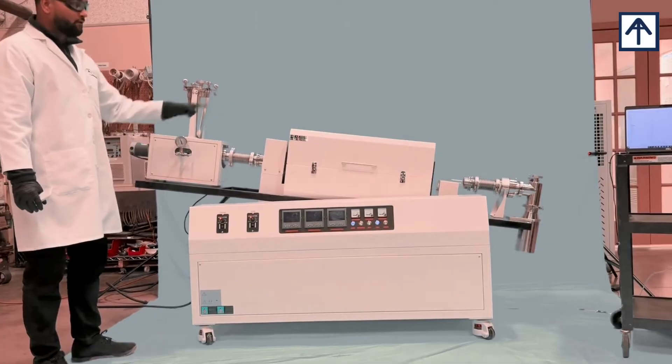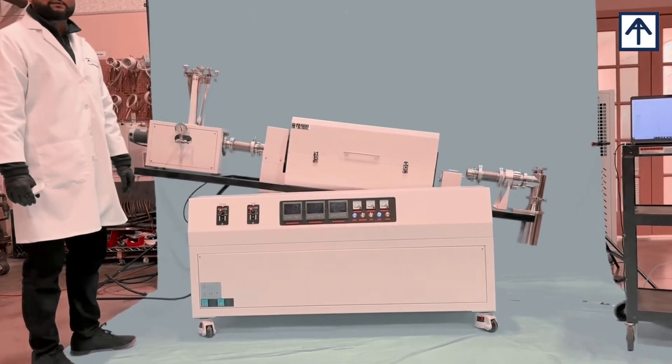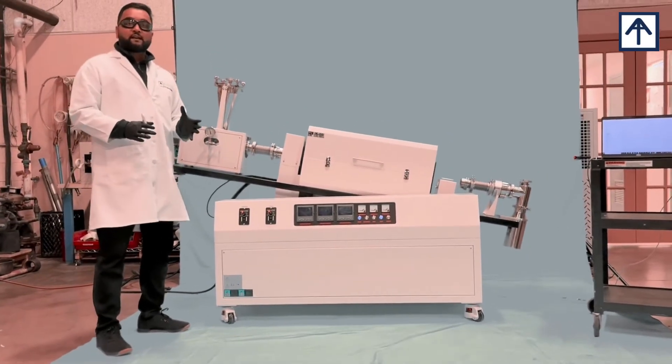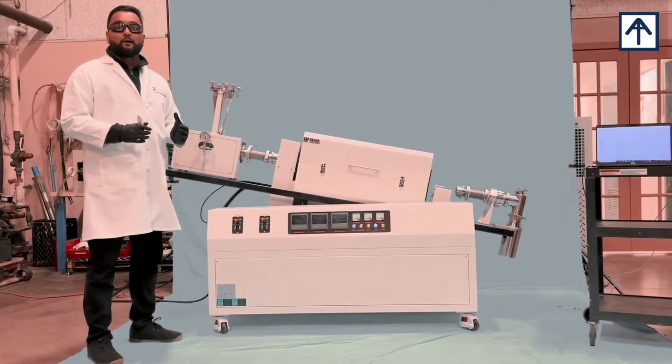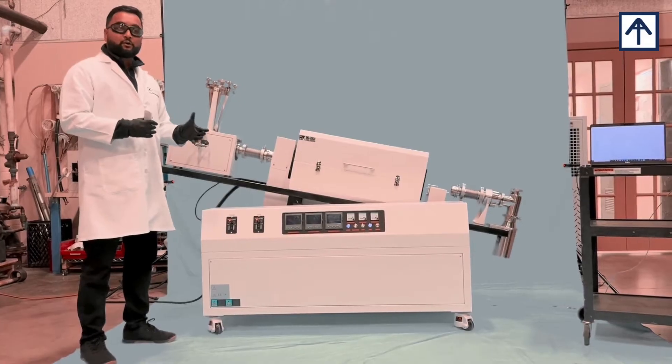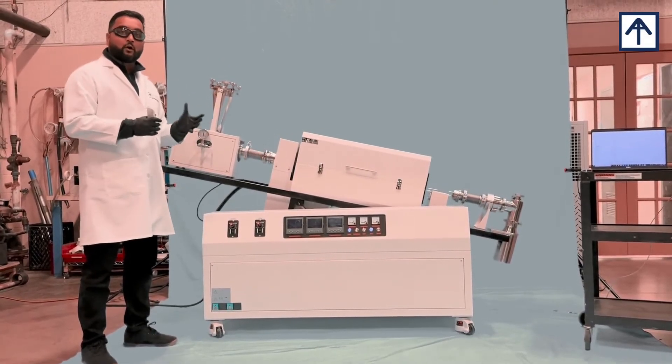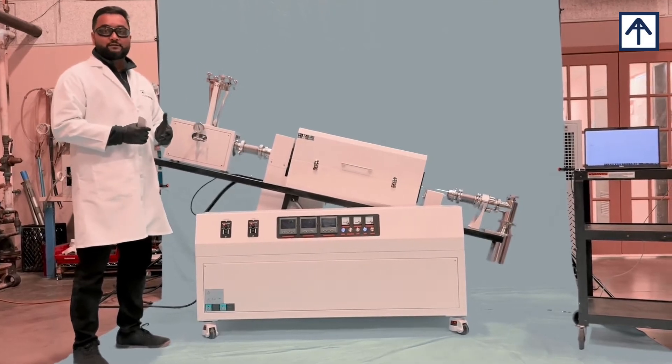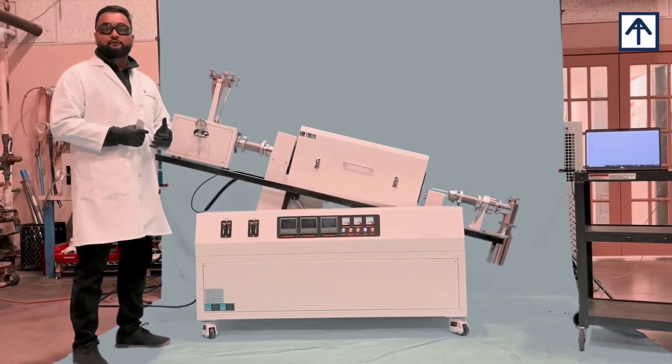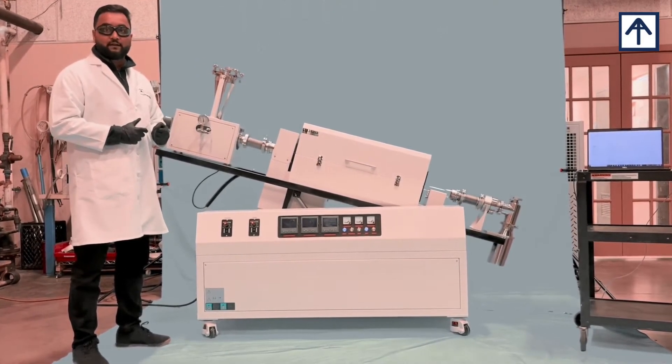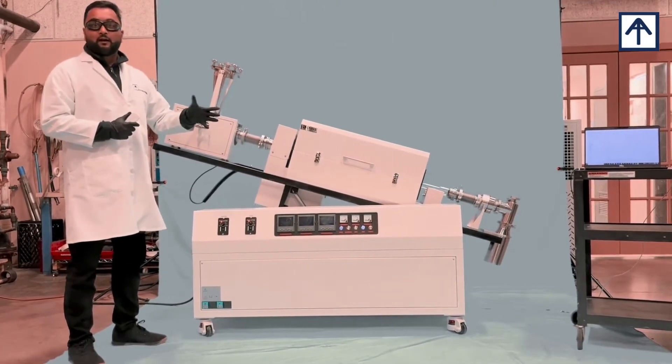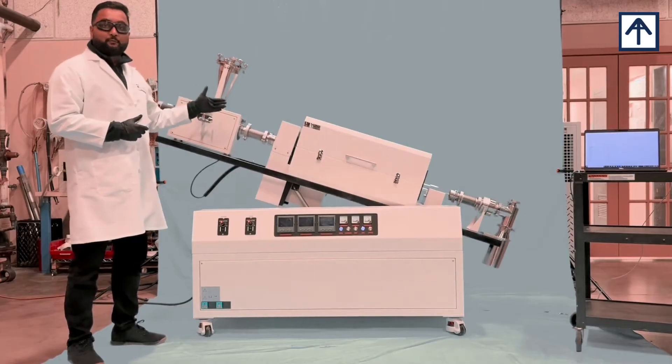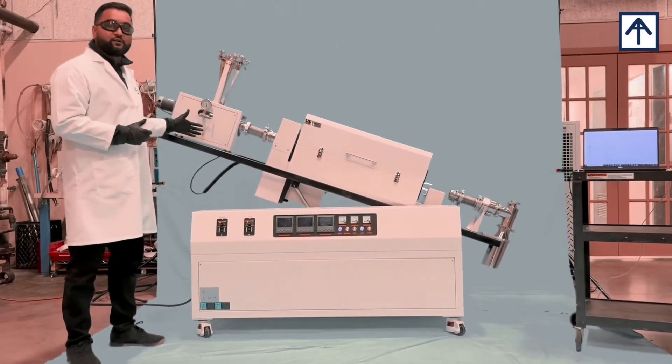While the system is still under vacuum, your inert gas application will still be active over time. The main primary use case for the machinery is to dry out powders. The powder can vary between carbon, carbon coke, battery anode cathode materials, and it can also be used for biochar analysis and pyrolysis, which is the most common application among these industries. You can dry out powder and collect the final assembly at the end while your system's under vacuum and inert gas.